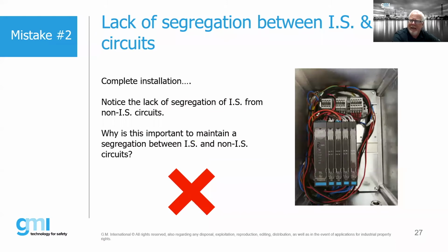But now here we have a situation where somebody has taken the wiring and made service loops. It's very easy to do this, and very easy to understand in the field, because we want to make sure that if we've done something wrong, we have plenty of excess conductors to make our connections. But now we've violated the distance requirement between IS and non-IS. Even though the design was fine, during our installation procedure we didn't have a good segregation between IS and non-IS circuits.